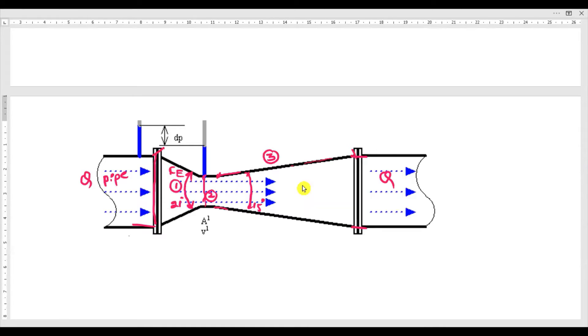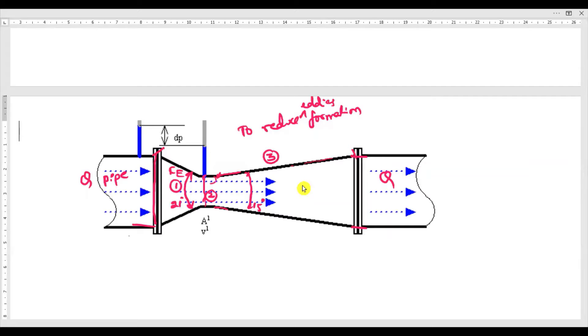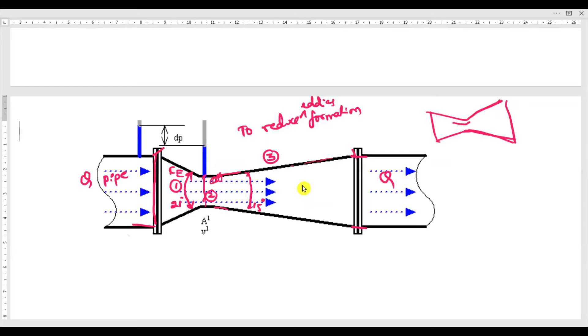The reason for the 15-degree angle is to reduce the formation of eddies. Eddies formation means there will be swirl motion in that area. If the area in the diverging end increases suddenly, fluid flow through it will cause eddy formation, resulting in backflow — instead of flowing towards section three, water flows in the reverse direction.